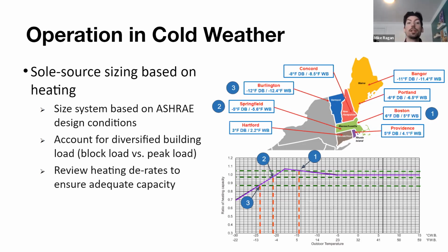And we're going to make sure to account for a diversified building load. We're not going to take a look at this as every single zone in the whole building is calling for full heating at once. If you have an office building with a conference room, if that conference room is fully occupied, that means that there's going to be other zones throughout the building that are unoccupied just by the nature and occupancy of the various zones. We are going to take that into account to make sure that at any given moment over the course of the day and any time of year, you're going to have your desired output.